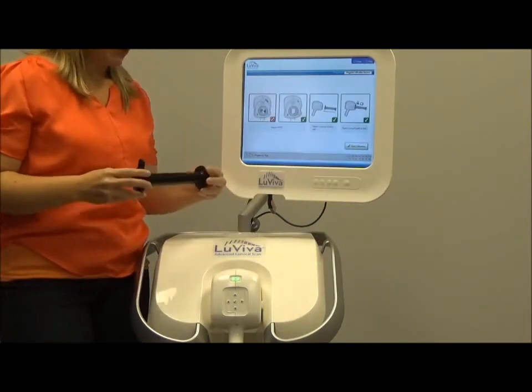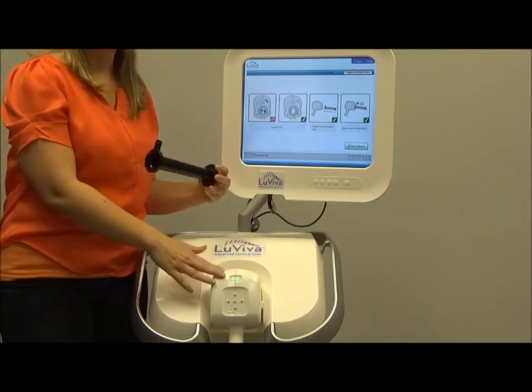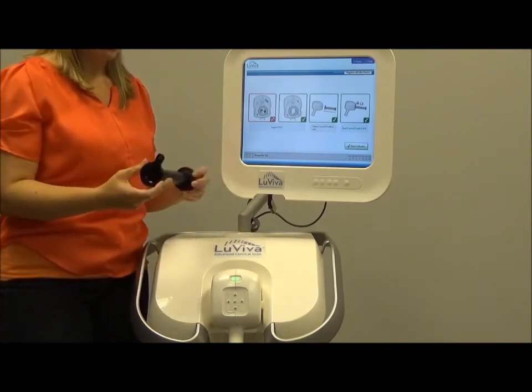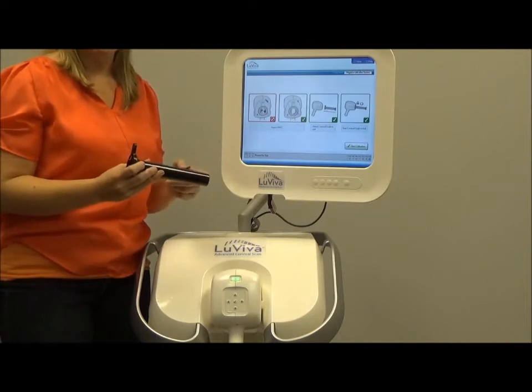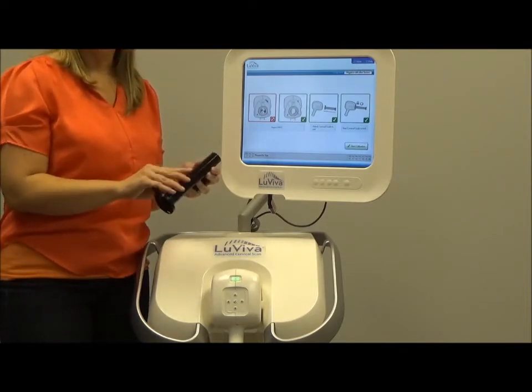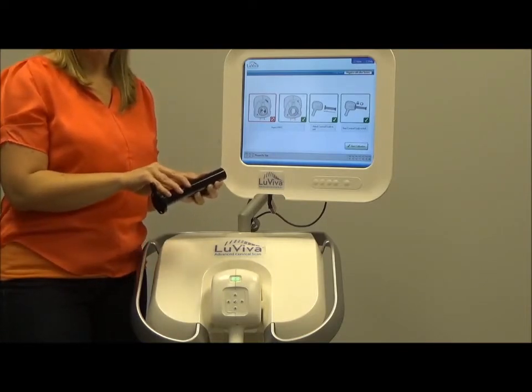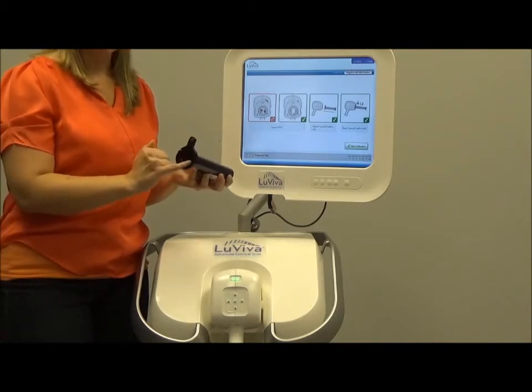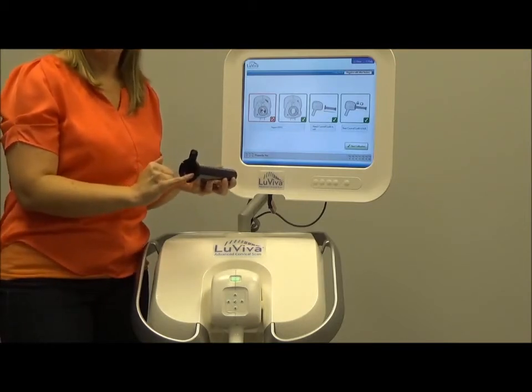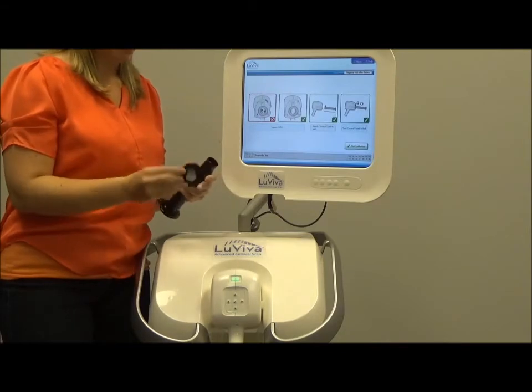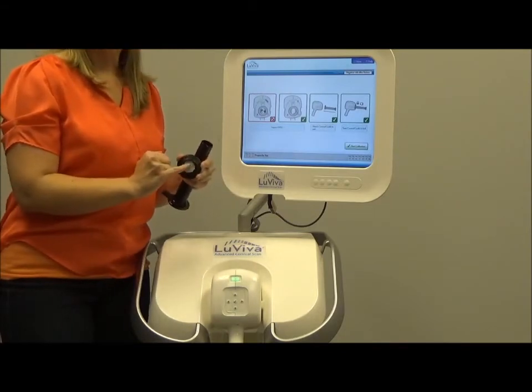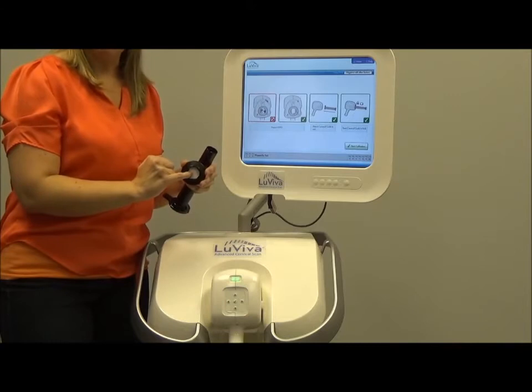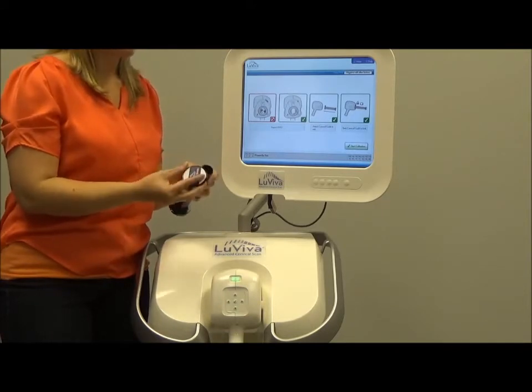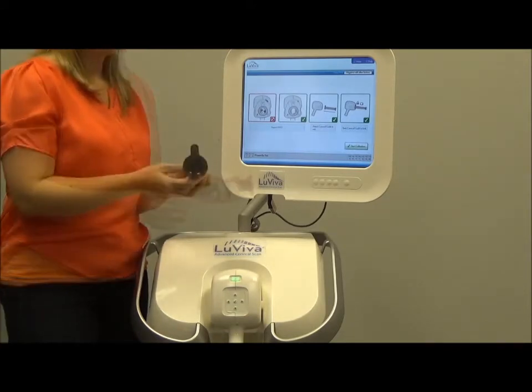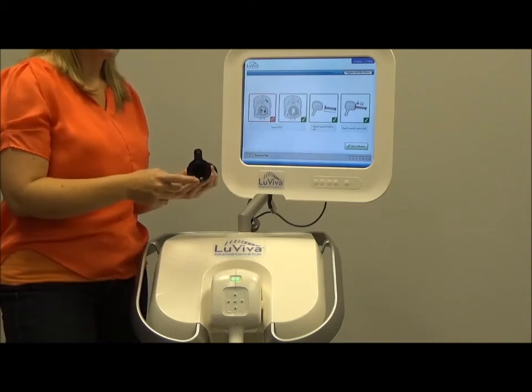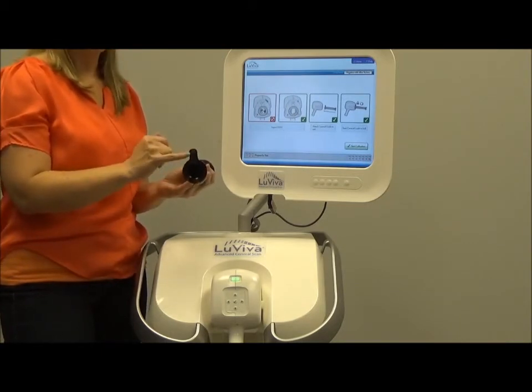For calibration, we're going to attach the calibration tube to the HHU. The calibration tube is simply a hollow plastic tube. It is black because we're trying to prevent light from going into the vaginal cavity. It does have a specialized coating within to prevent reflection of light. And then the cap itself has special paper. This paper is used in essence for white balance in calibration to make sure that we are getting the correct results. On the side that attaches to the HHU, you'll see there is a flange with a green dot.